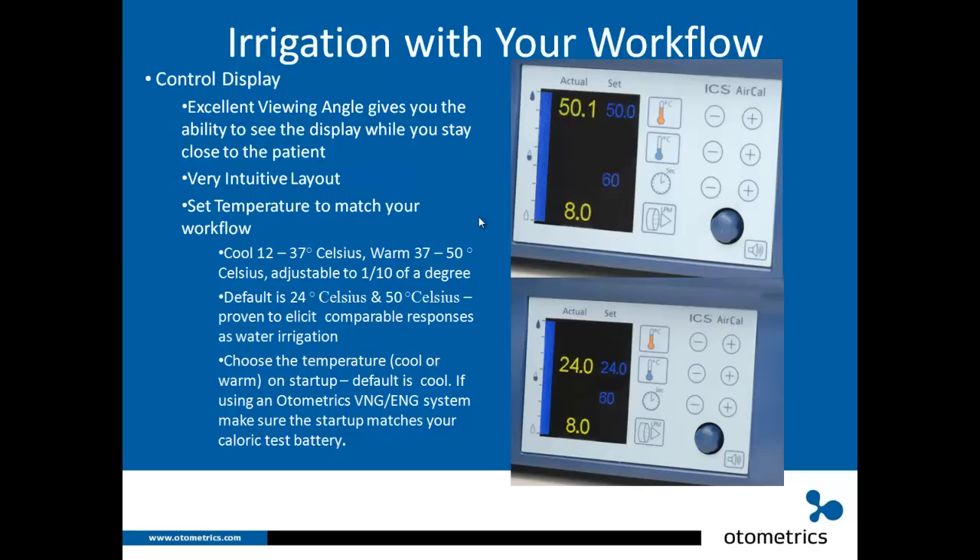You can choose which temperature the ICS AirCal starts up with — cool or warm. The default startup is cool. If you're using an Otometrics VNG/ENG system, make sure the startup matches your caloric test battery. If you start with left ear cool, make sure your irrigator starts with cool; if you start with right ear warm, make sure your irrigator starts up in warm.